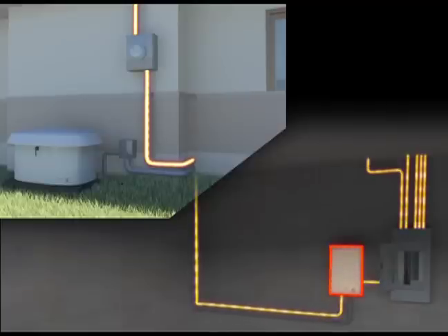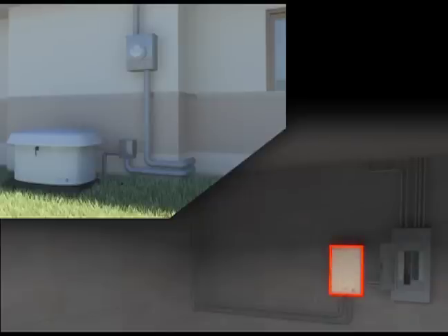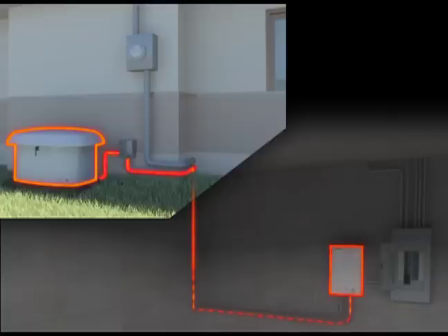When utility power fails or drops below an acceptable level, the transfer switch senses a lack of power and automatically starts the generator. Within 10 seconds, the transfer switch automatically disconnects utility power and connects to the auxiliary power provided by the generator.